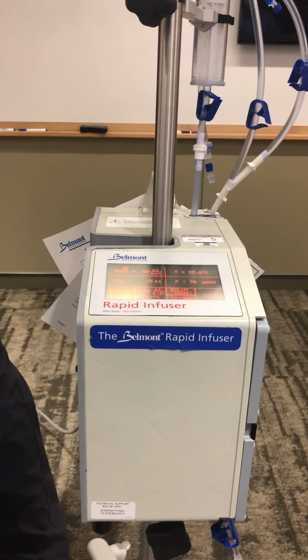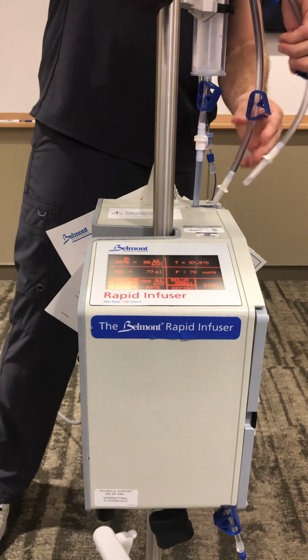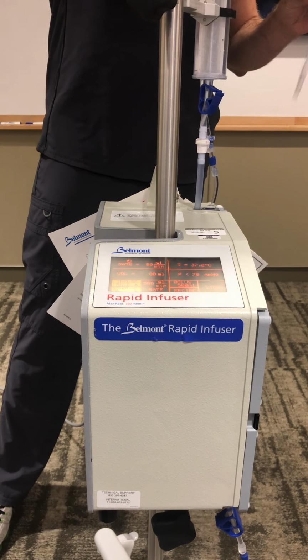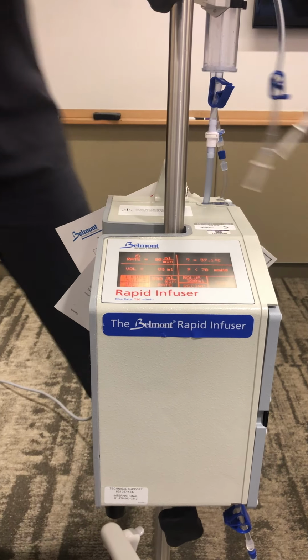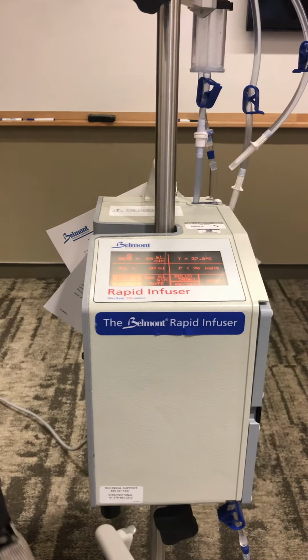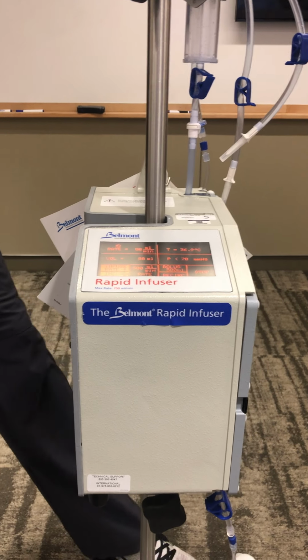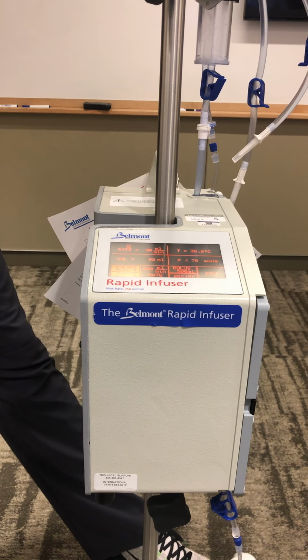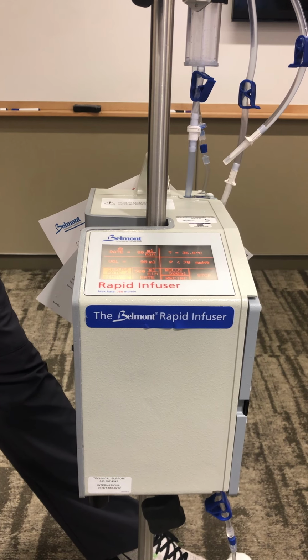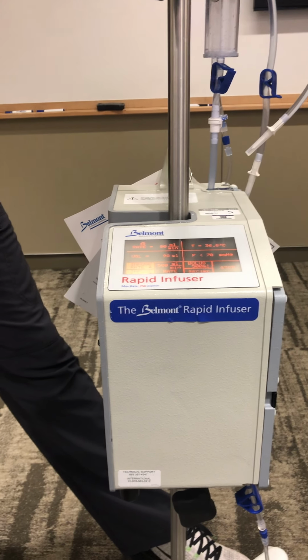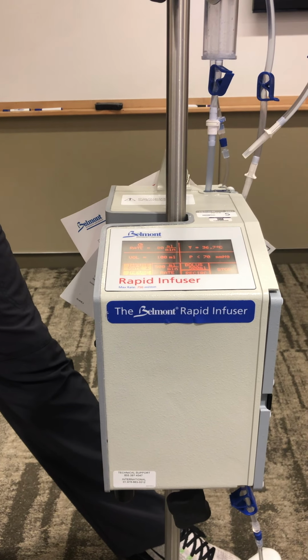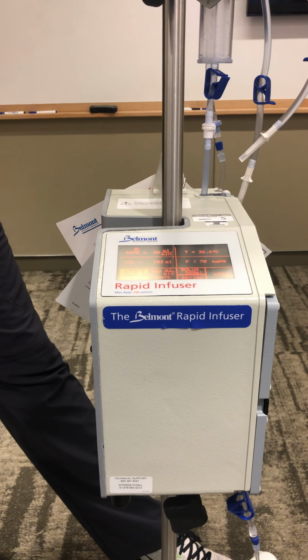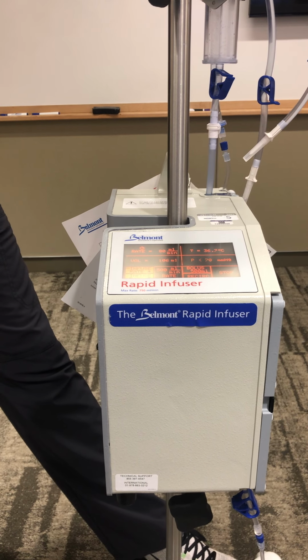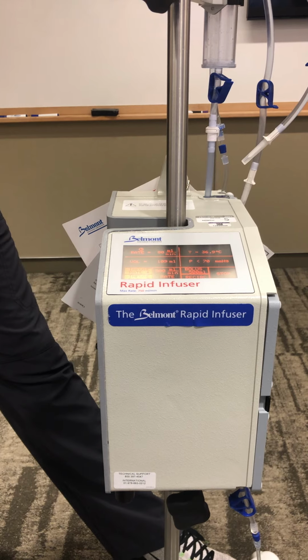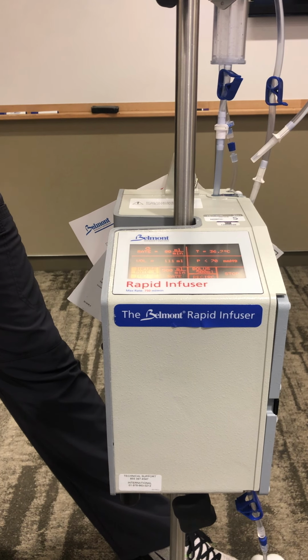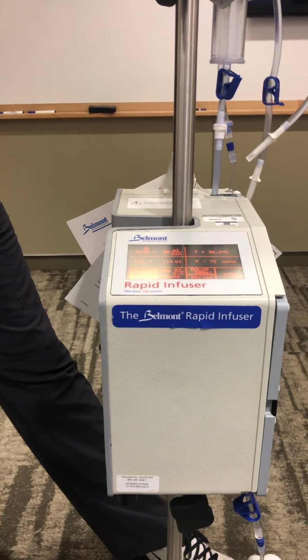The thing about that, though, that I do like to mention: it does not have the capability to cool. So if you take fluids out of a warmer and put them in here, we have an over-temp alarm at 39.5. It's an easy fix: just don't put warm fluids in there. If you put in fluids above that threshold, it will instantly give you an alarm, and it will not let you proceed until the fluids are below that. Again, it's all for patient safety.